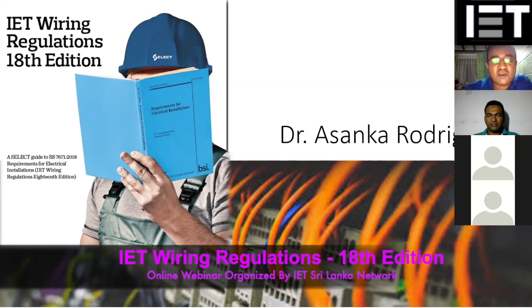Thank you, Doctor. Next question is, if we connect the earthing of the surge protection system to the building earth, isn't there any impact to the equipment during a surge? Because when you look at the basic concept, equipment is damaged because of potential difference. That's why you have to have surge protection, because the surge protection has the Up value, which is the voltage protection level. So if you select the voltage protection level correctly by considering the insulation level, the Uw value of your installation, there won't be any problem connecting the lightning protection system, from the air terminal, to the earthing system, because that will create equipotential.